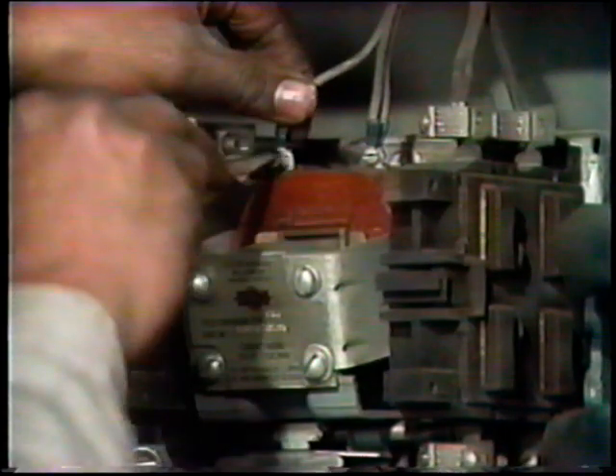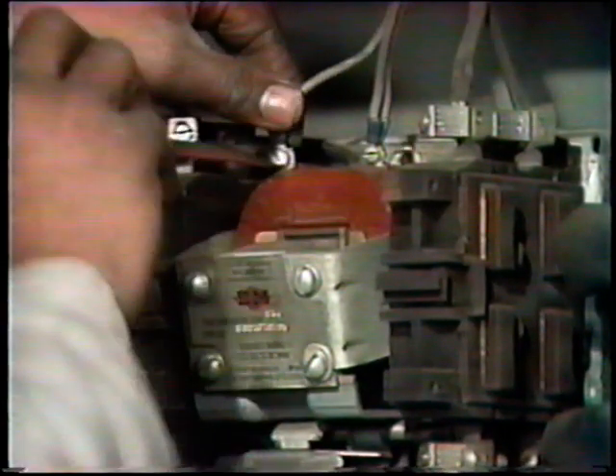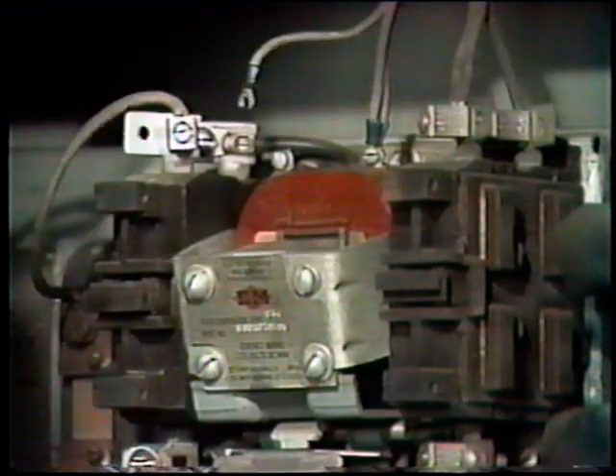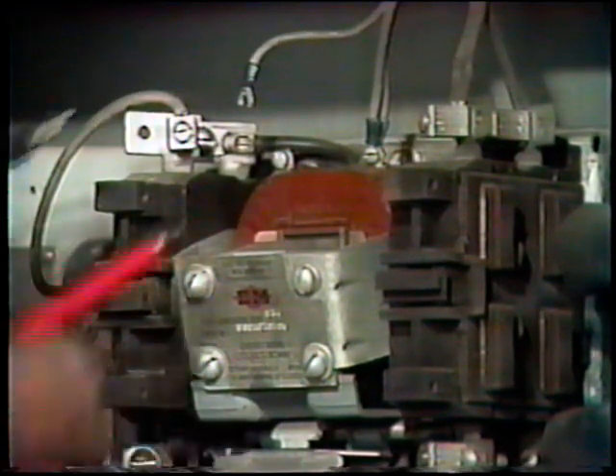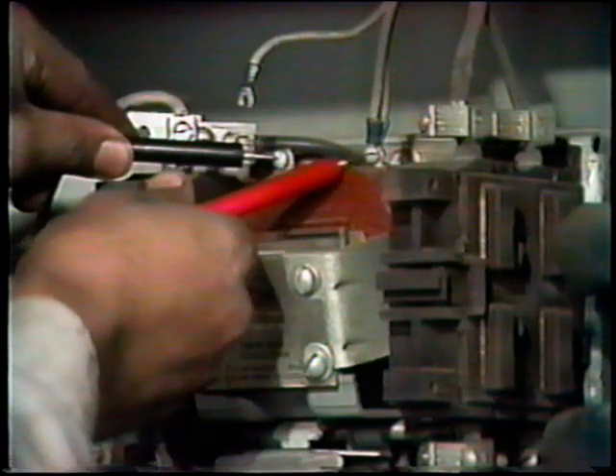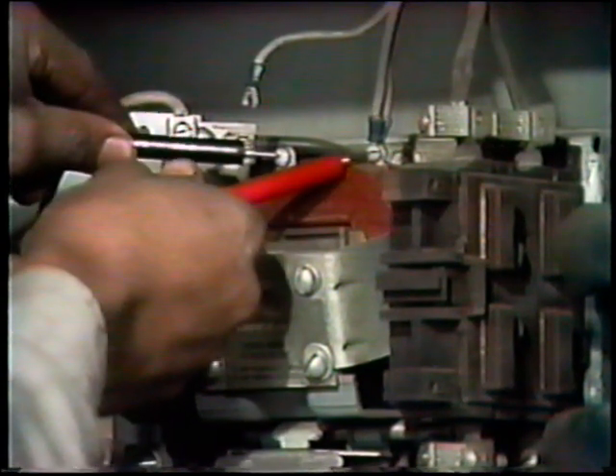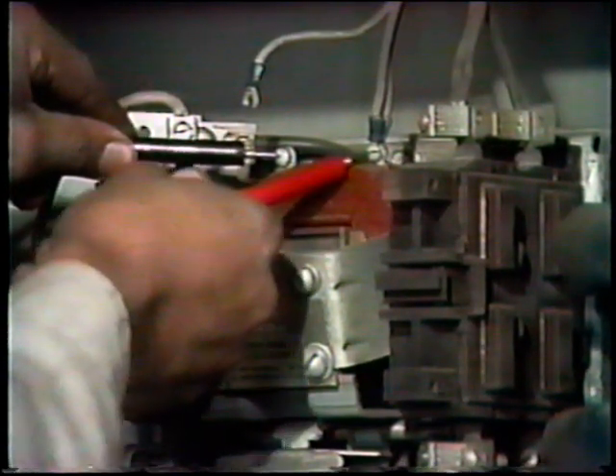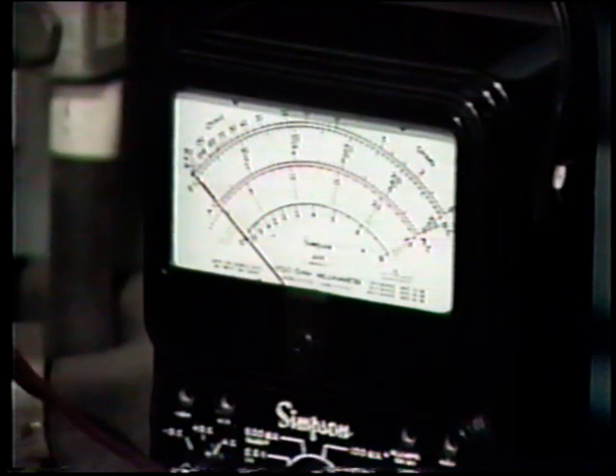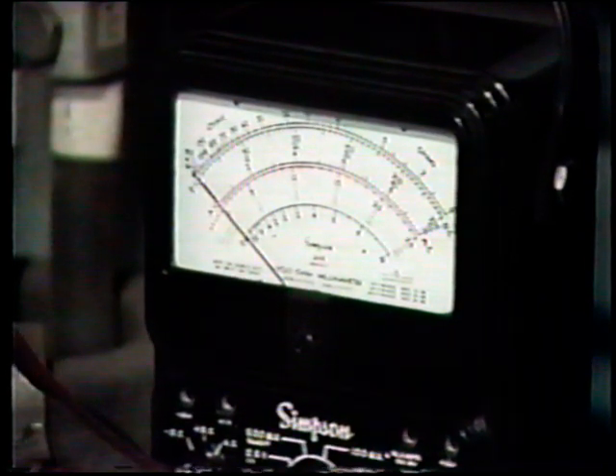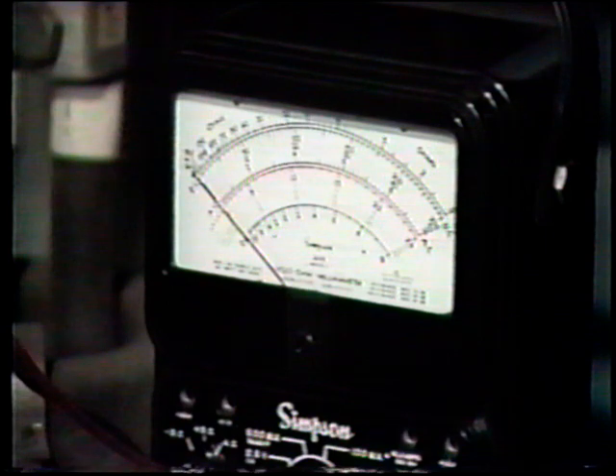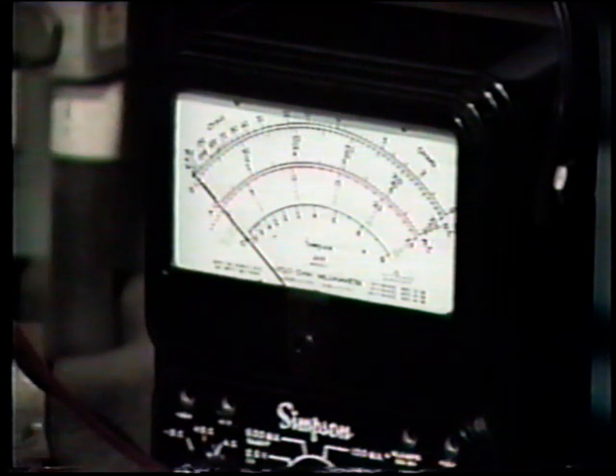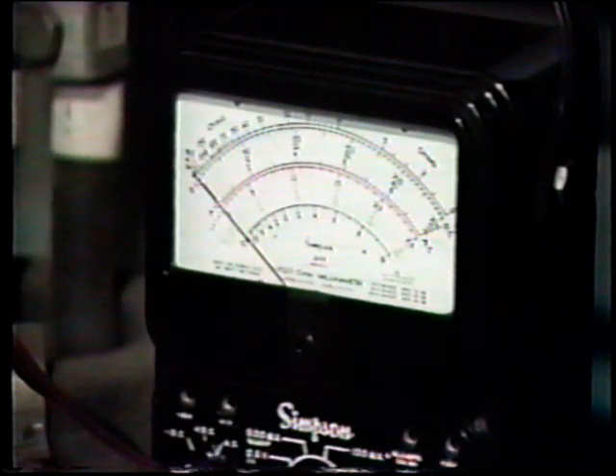Then one of the electrical connections of the field relay coil is disconnected. The multimeter probes are placed at each electrical connection point of the coil, and a reading is taken. A high resistance reading on the multimeter indicates that an open exists in the coil. A low resistance reading indicates that there's a short. Here, the reading is infinite resistance. An open exists in the coil.